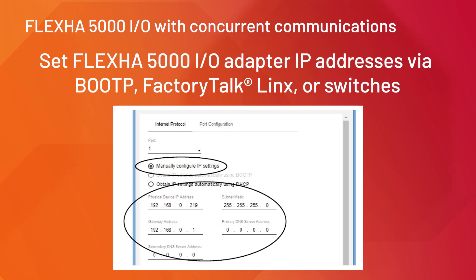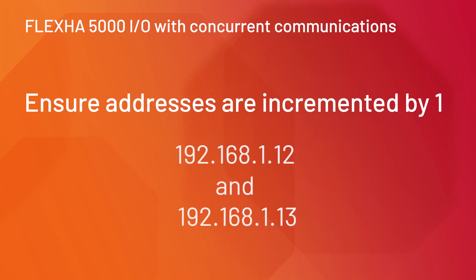Set the FlexHA 5000 I/O adapter IP addresses via BootP, FactoryTalk Linx, or switches. Manually configure the IP addresses and confirm they are incremented by one. For example, 192.168.1.12 and 192.168.1.13.